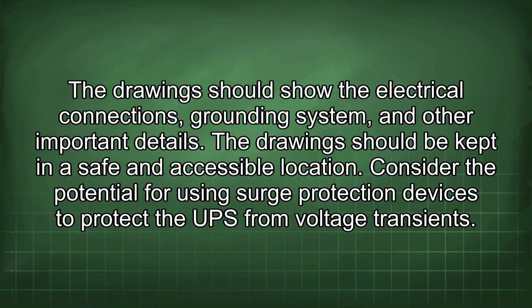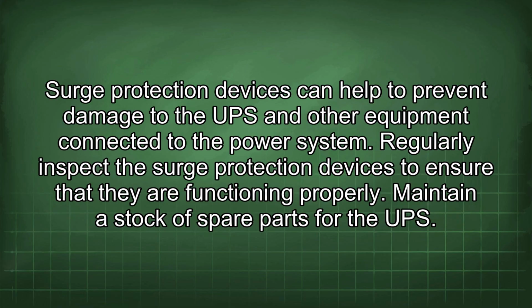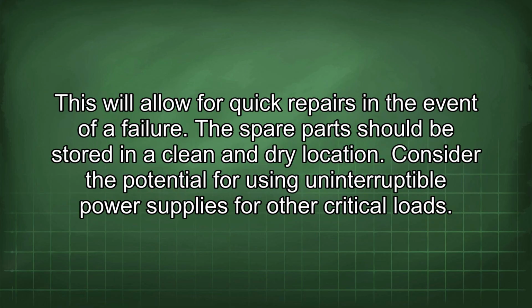Consider the potential for using surge protection devices to protect the UPS from voltage transients. Surge protection devices can help to prevent damage to the UPS and other equipment connected to the power system. Regularly inspect the surge protection devices to ensure that they are functioning properly. Maintain a stock of spare parts for the UPS. This will allow for quick repairs in the event of a failure. The spare parts should be stored in a clean and dry location.